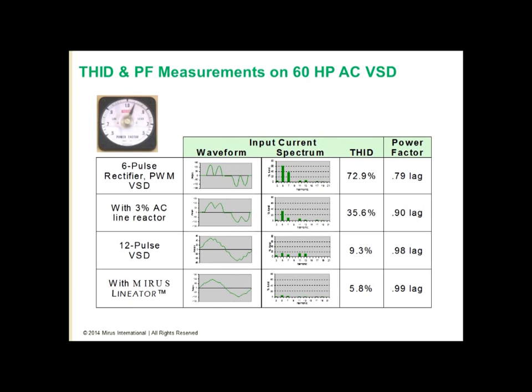The 12-pulse VFD, which uses a phase shifting transformer on the input to get cancellation of certain harmonics, predominantly the 5th and 7th, is shown in the next row. We have residual harmonics of 5th and 7th, we have 11th and 13th. Total harmonic current distortion now is just under 10%, and power factor is improved to 0.98.